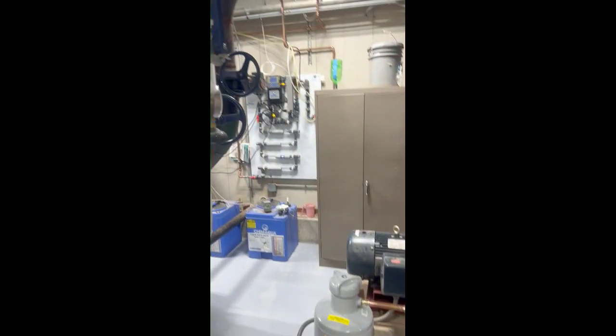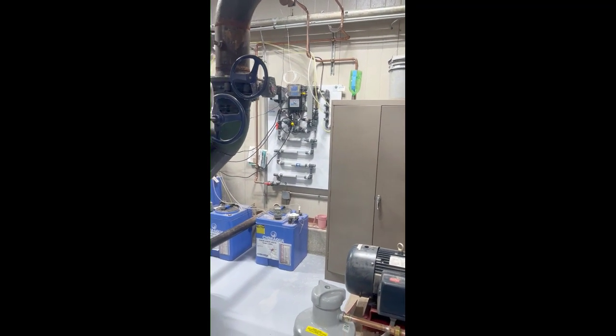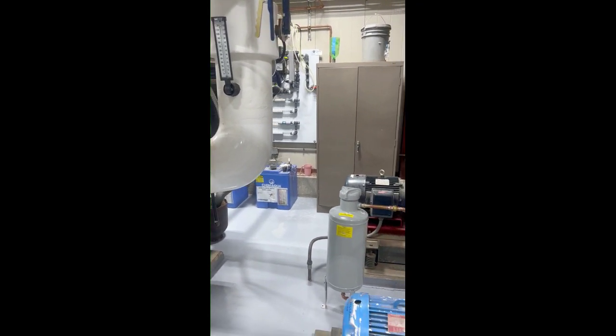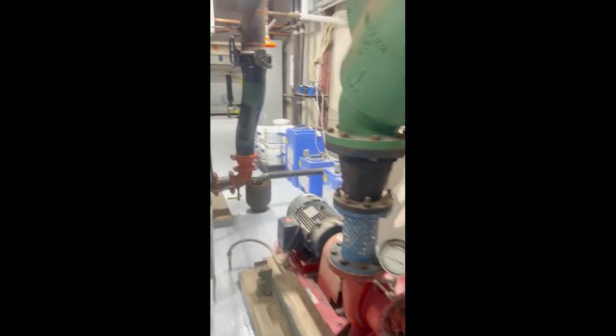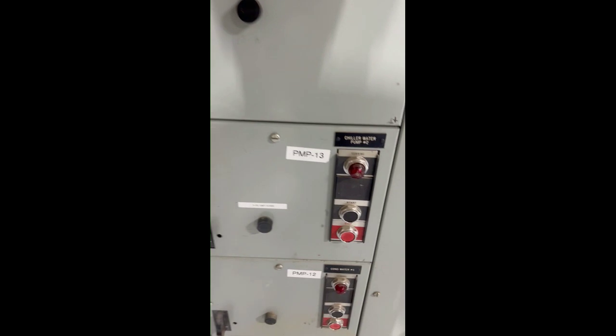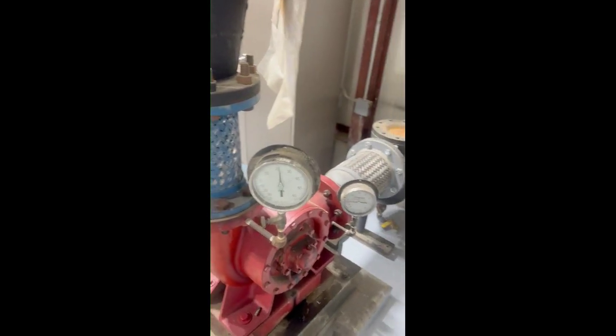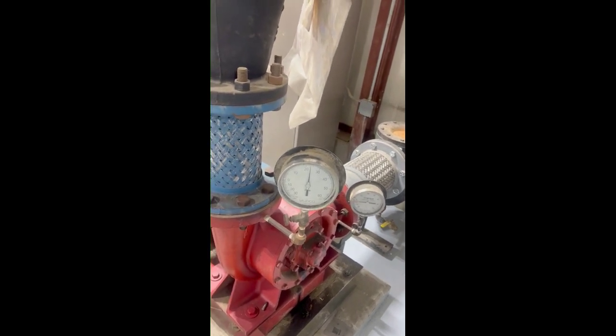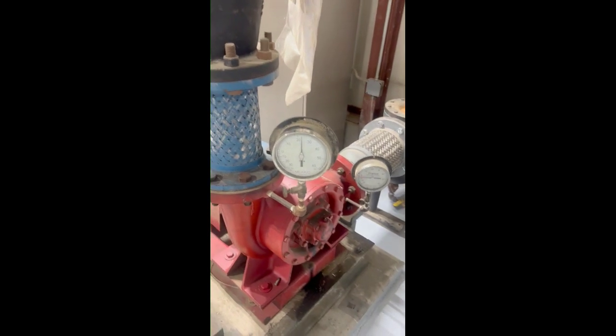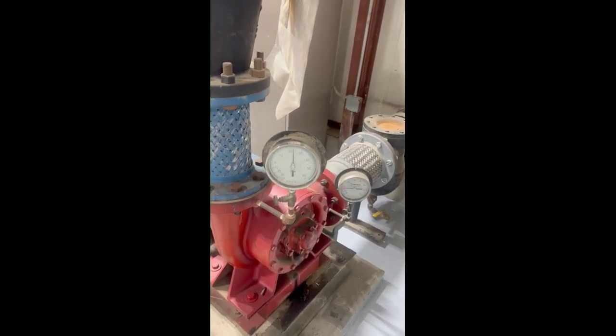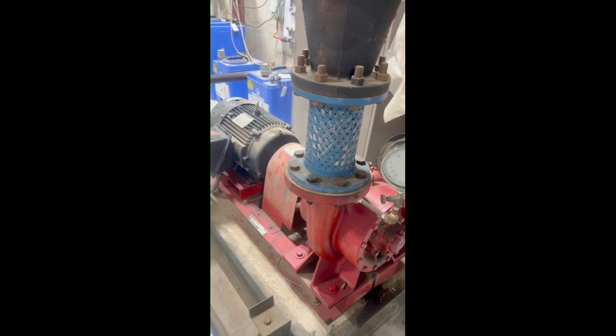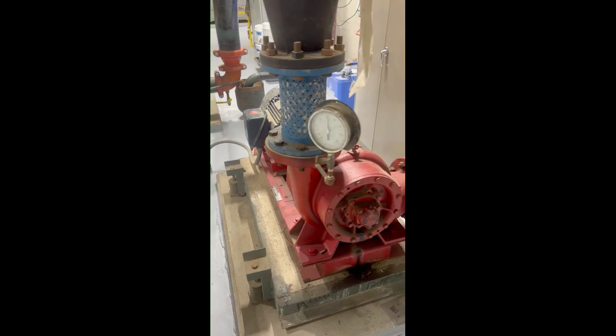They're not leaking. As well as my chemical feeders around the corner to make sure that my water tower is also well treated chemistry-wise as far as the biologics, the Legionella, and bacteria, and algae, and all that kind of stuff. So that's what the chemical feeds for a water tower do. And if I want to, I can turn on my condenser water pump. That pump is the main. The reason I'm doing that is to pump through the tank. The tank that's outside, I'll show you here in just a second, is basically idle water just sitting. So I need to stir it every once in a while before we're using it, just to keep the chemicals from settling out.